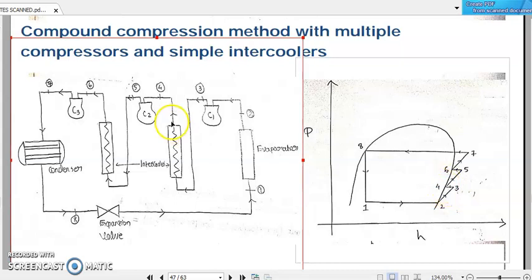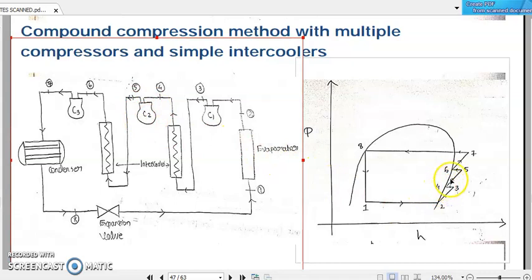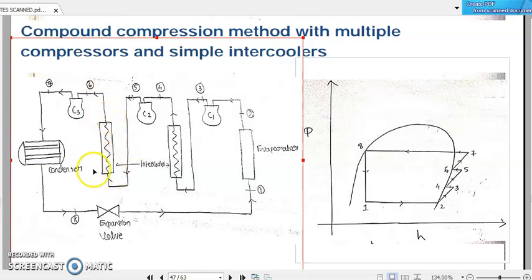After point four, the refrigerant enters the second stage compressor C2. Process four to five is the second level of isentropic compression by C2, represented as an inclined line in the pressure-enthalpy diagram. After coming out from C2 at point five, the refrigerant again enters the intercooler where it gets intercooled. We draw a horizontal line from five to six, marking point six on the saturated vapor line, as five to six represents the second intercooler.